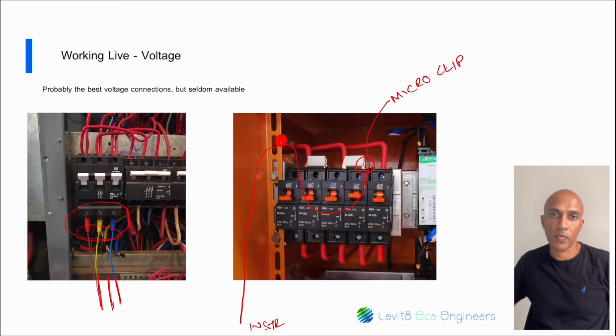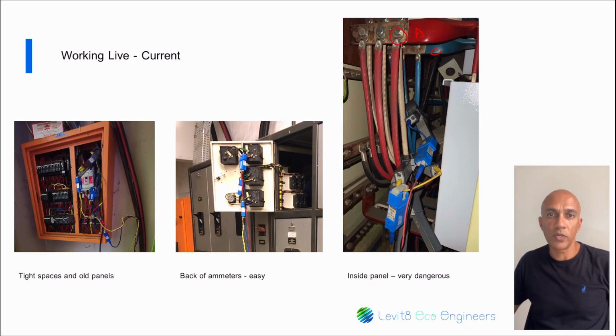Now, for current, also ensure that you keep your safety gloves on at all times. Sometimes getting to the feeder cable or wires may be hazardous, and your hands could come into close proximity to live parts. This is especially true if you are required to clamp onto bus bars that are slightly behind the circuit breaker.